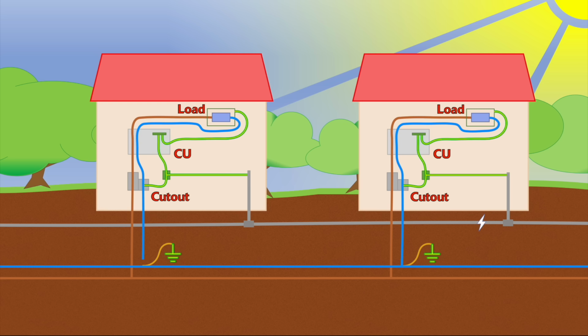What's this? Next door's water pipe. It travels along there, comes to the neighbour's bonding conductor, travels to the main earthing terminal, and from there to the service head, where, lo and behold, it can travel back down the neighbour's combined neutral and earth conductor in the supply cable and make its way back to the transformer. So the current that should flow down the neutral has become diverted through next door's supply. That's where we get the phrase diverted neutral current.